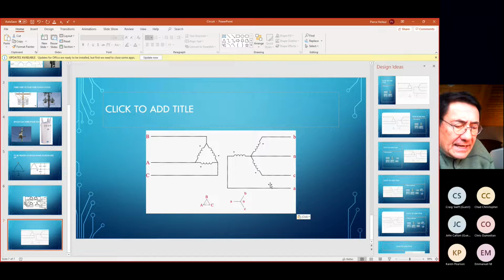So the drive, as a standard, has a metal oxide varistor between each phase of its input. And if you look carefully on the input of the drive, preferably not when the drive is powered up, you will see these green or blue or red lollipops, and you will see that each leg of the 3 lollipops are between a phase. These are not in line as far as the power is concerned, they're phase to phase. So they're there to clip voltage. And the way that a metal oxide varistor works, varistor is a shortened form of variable resistor. And as the voltage goes up, the varistor decreases its resistance.